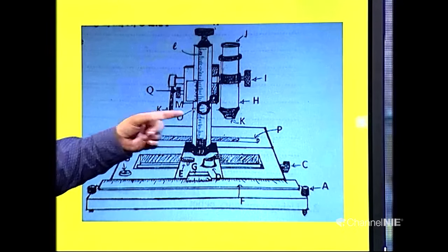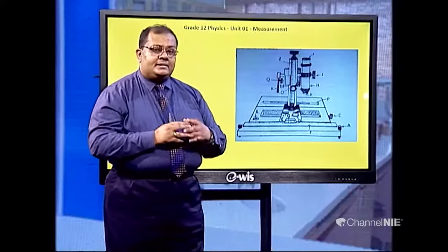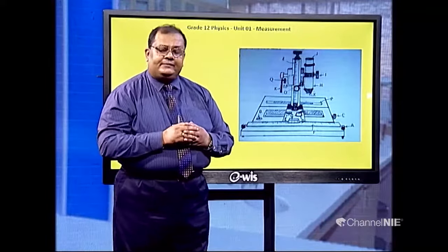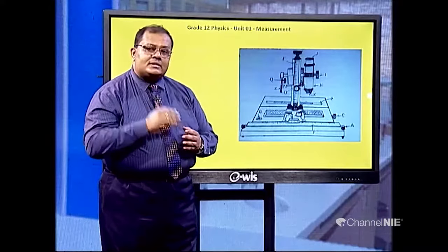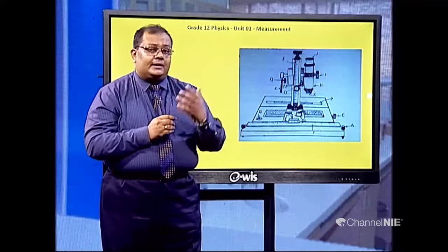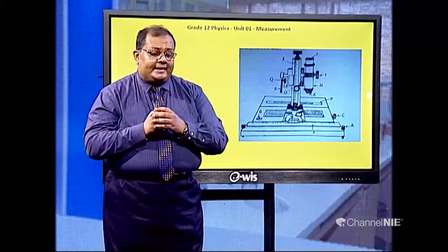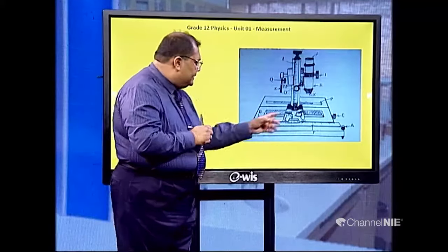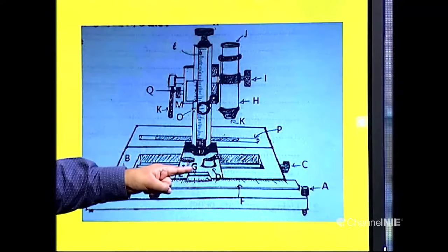And here, the least count of this instrument is 0.01 millimeters. Therefore, the distance between two consecutive lines will be very small. When you are taking readings, it is hard to find the correct coinciding line. To take those readings sharply, we use a magnifying glass. This is the magnifying glass of the horizontal vernier, and this is the magnifying glass of the vertical vernier.